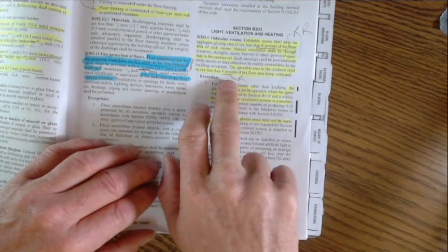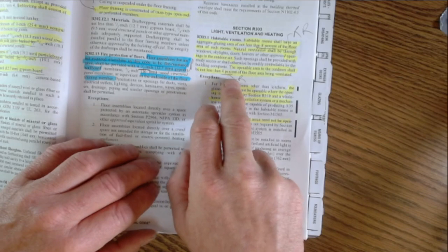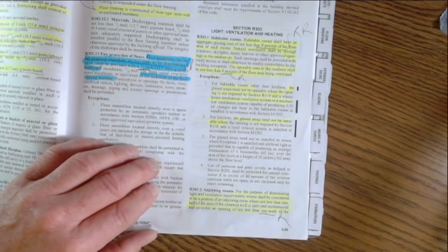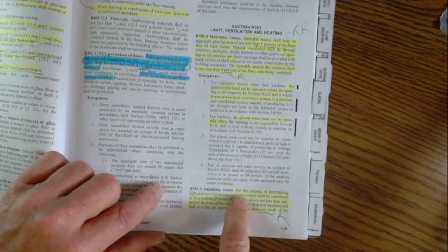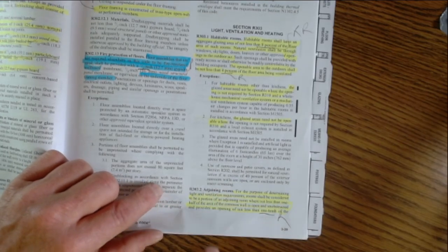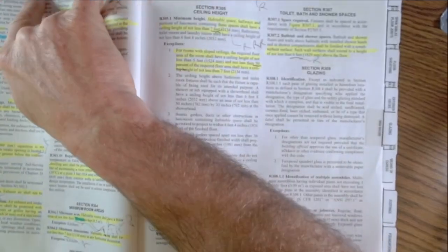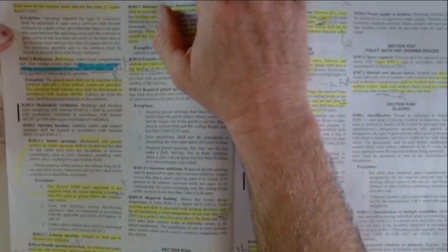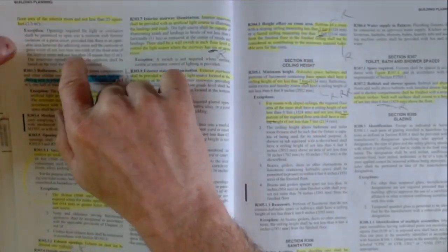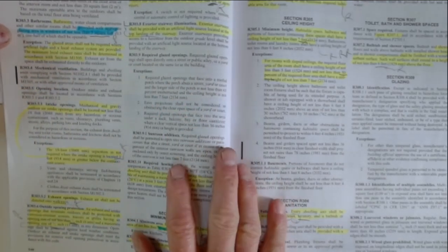If you're relying on natural ventilation, you need 4%. So if you have a 100 square foot room, it's 4 square feet that's the answer. Adjoining rooms, know this. This is important. If you have a room that's not vented, there's an allowance for you to use either 1/10. Anyway, I'm not going to go into details, but just know what that is, because that's the exemption. Yeah, this is the bathroom section. You can use 3 square feet here.